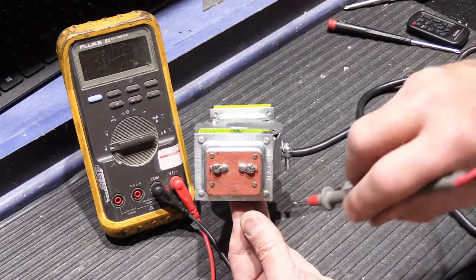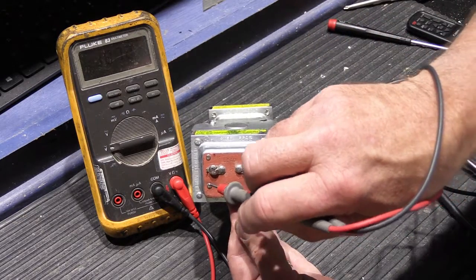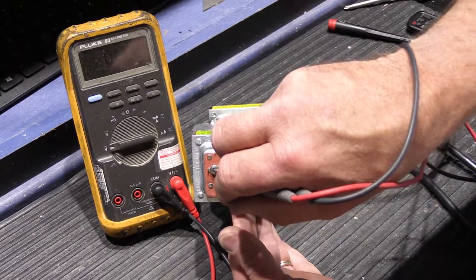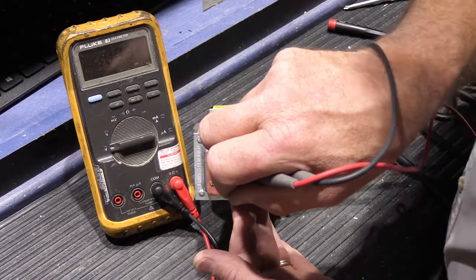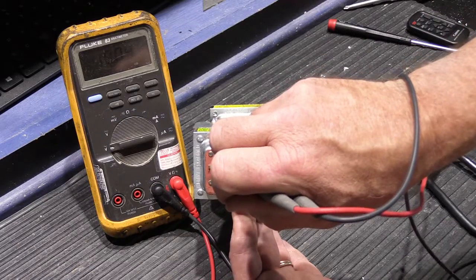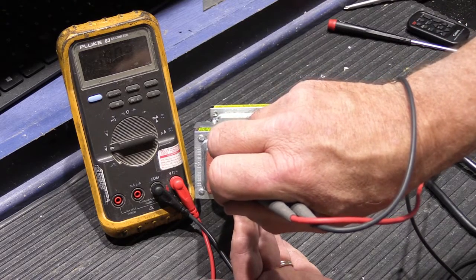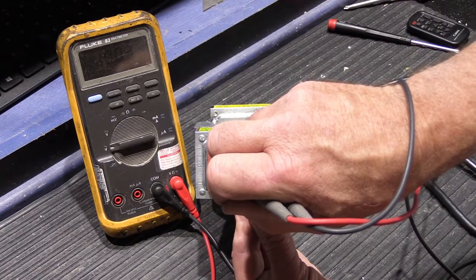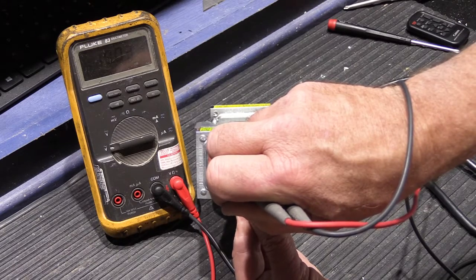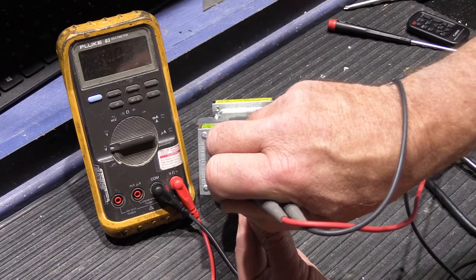So you put your voltmeter on AC, put one probe on one screw and the other probe on the other screw, and measure the voltage. Again, we have 19.03, so that's fine. Now let me show you what happens when transformers are overloaded and what your multimeter will tell you.